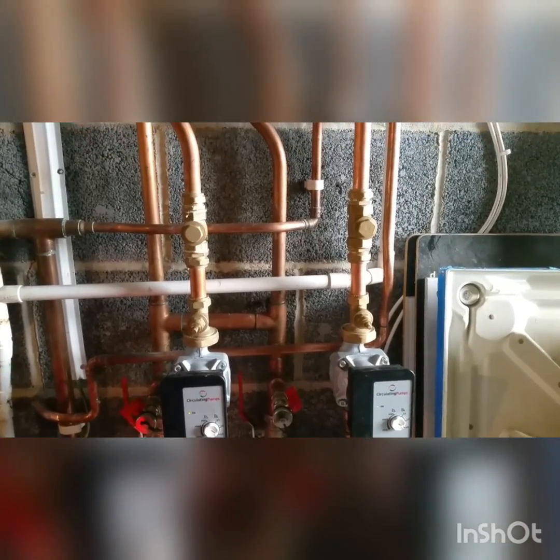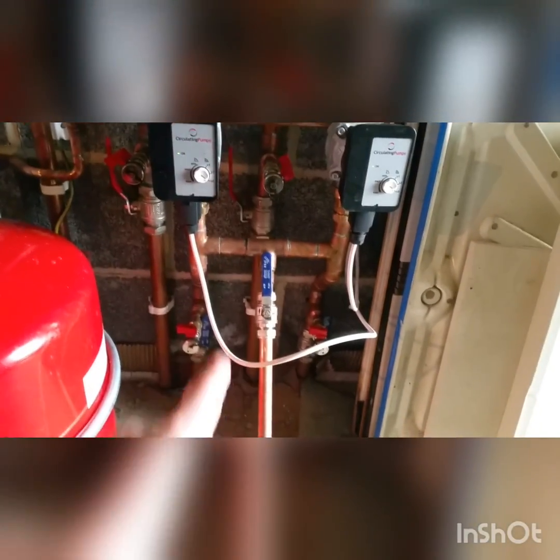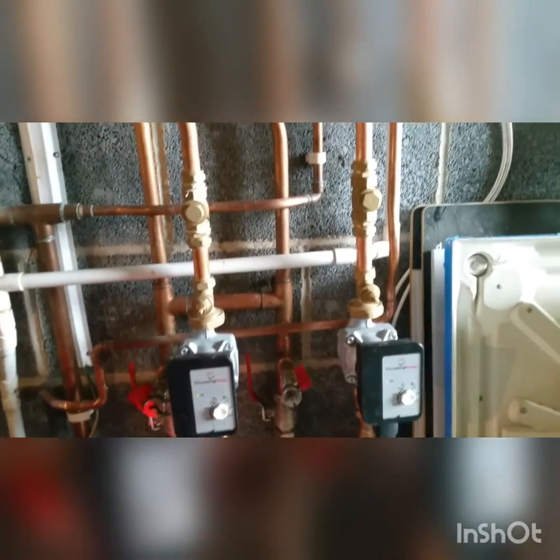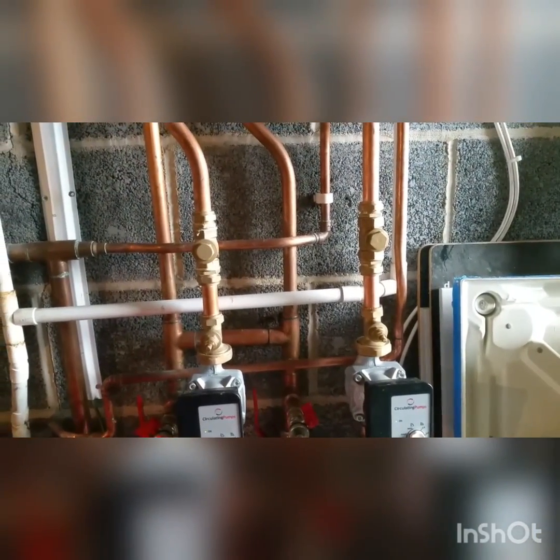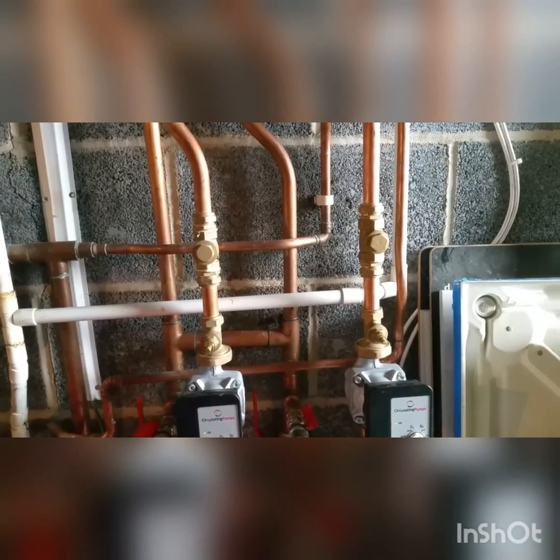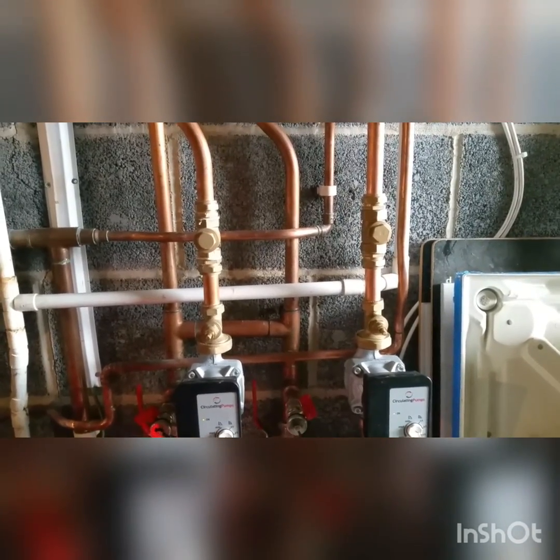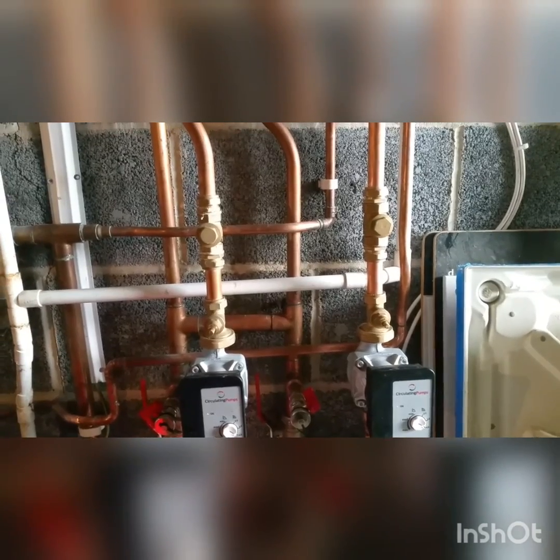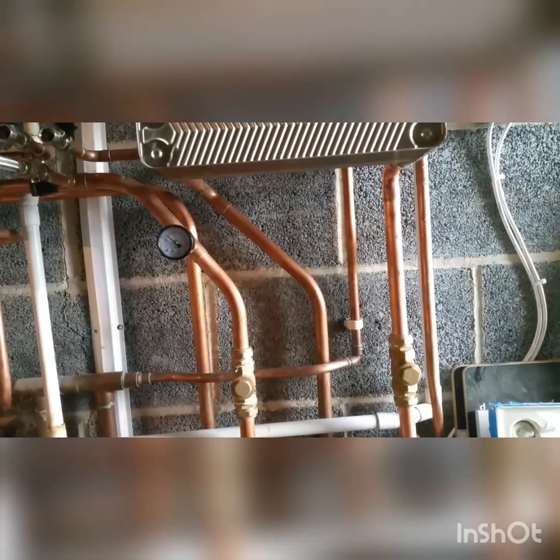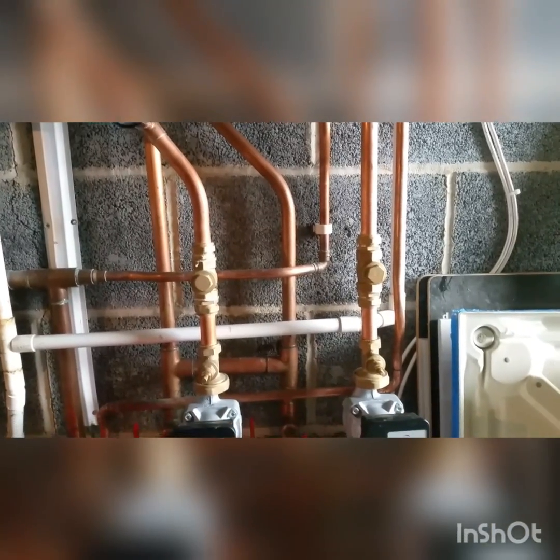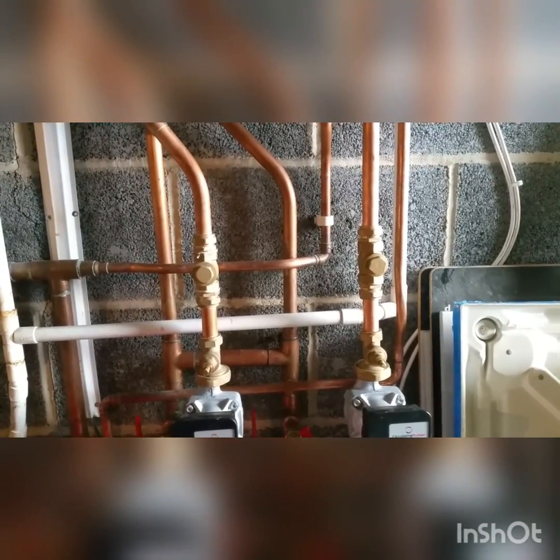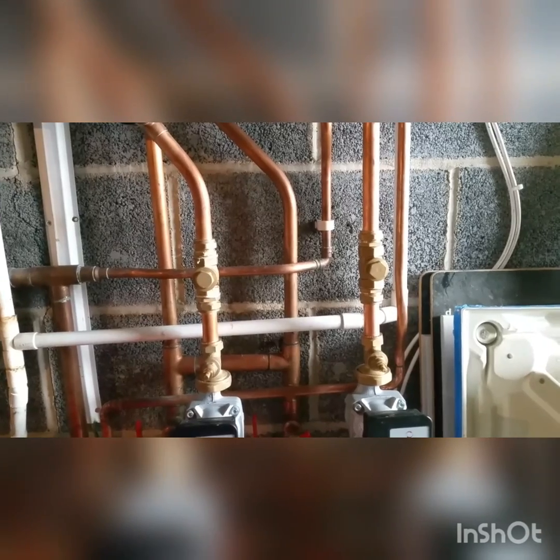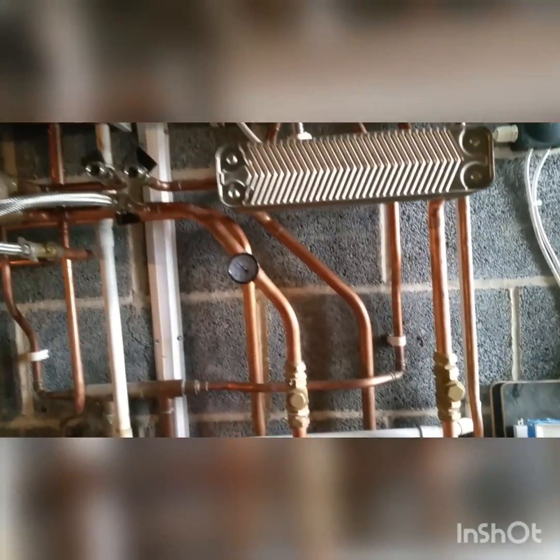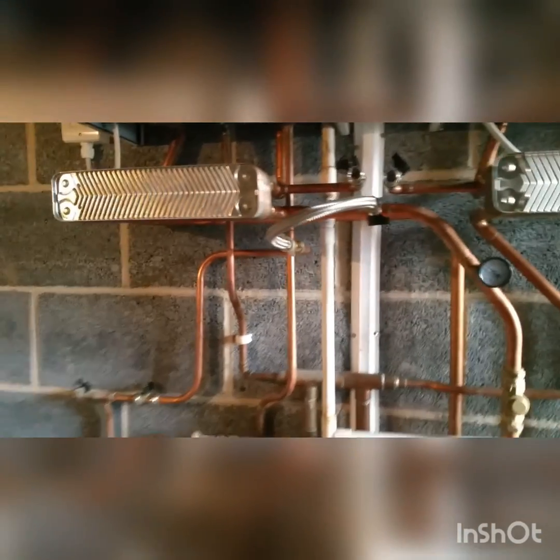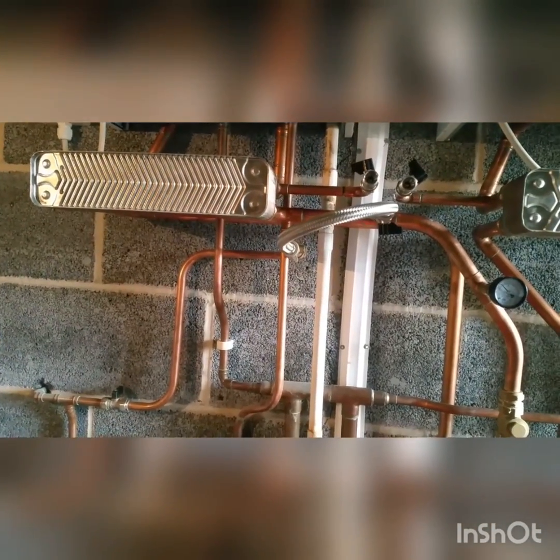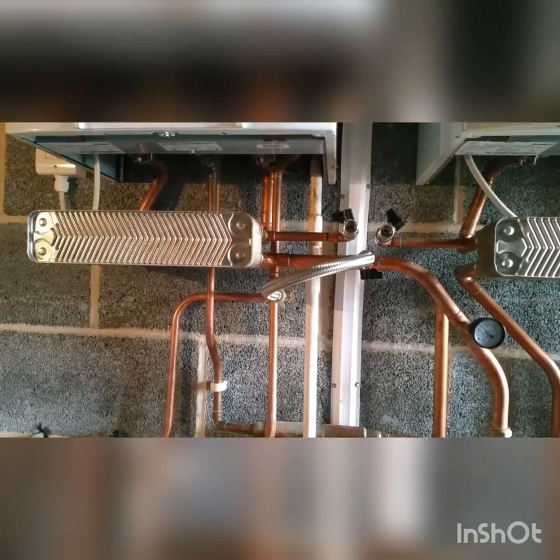Got non-return valves in there, just to save any problems with clashing pumps. There's a phenomenon that happens, I know, on the Viessmann boilers when you put them on cascade systems, where you have to have a non-return valve on them, where you get some peculiar goings on, and I don't really understand why you do, but the cure is a non-return valve. So I just made the assumption that I might have a similar problem here and put these in just in case, but I don't actually quite understand why. If anyone knows why, I'd appreciate the information. But for now I've put them in and everything's working really well.